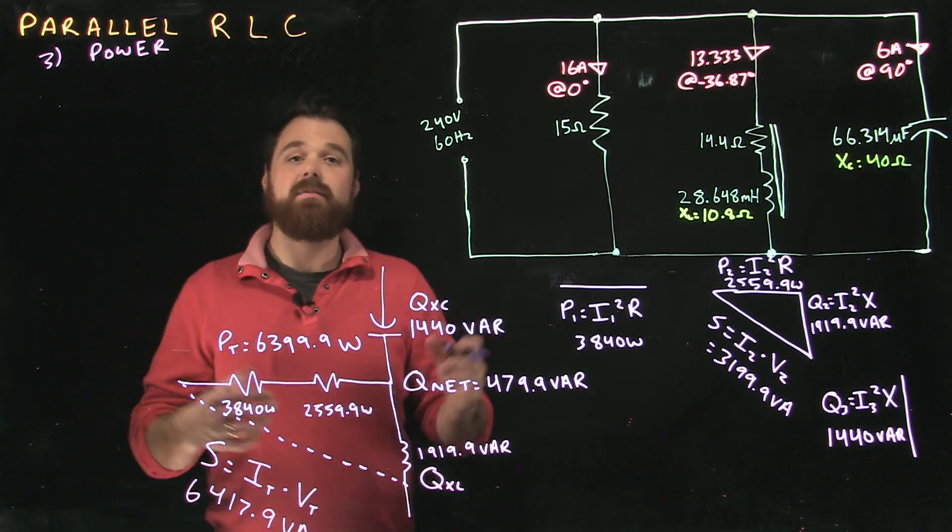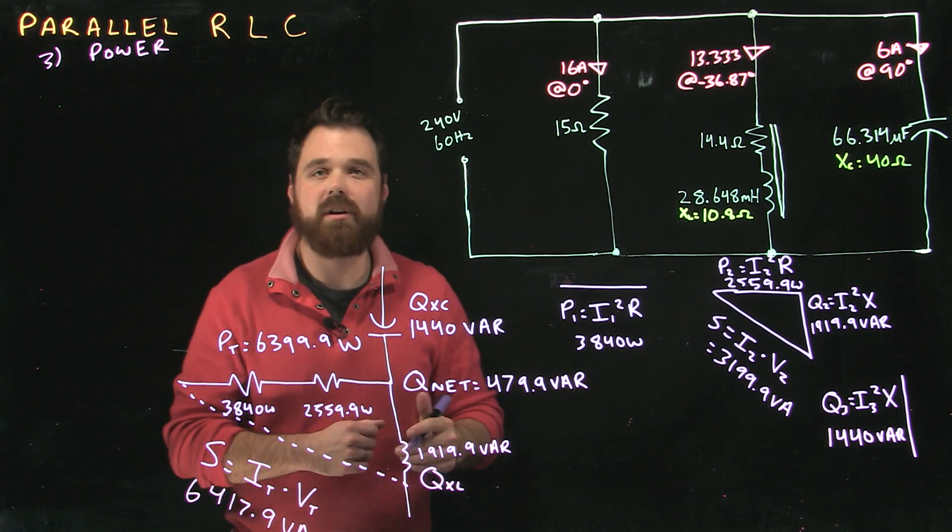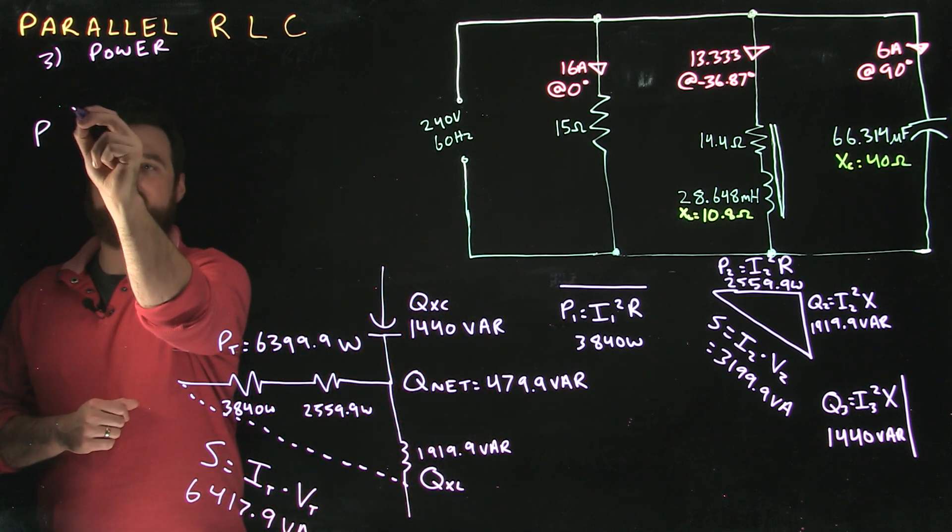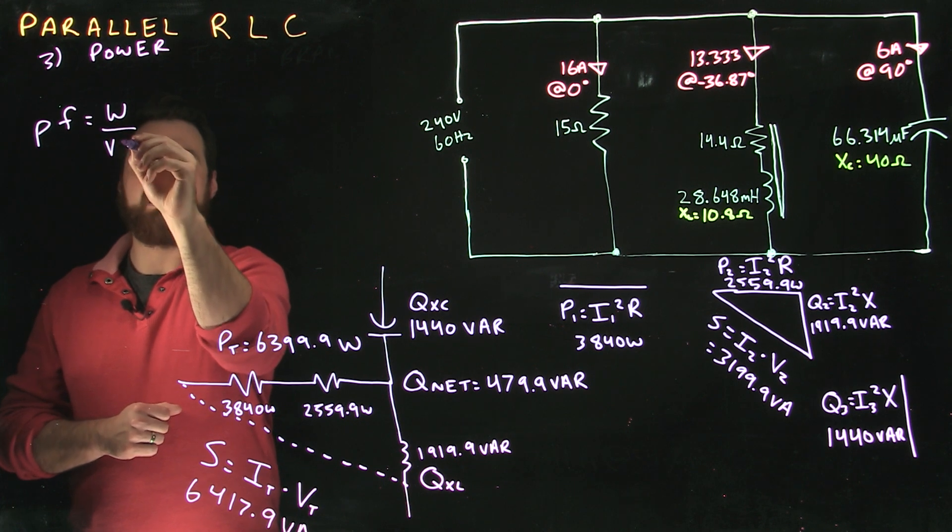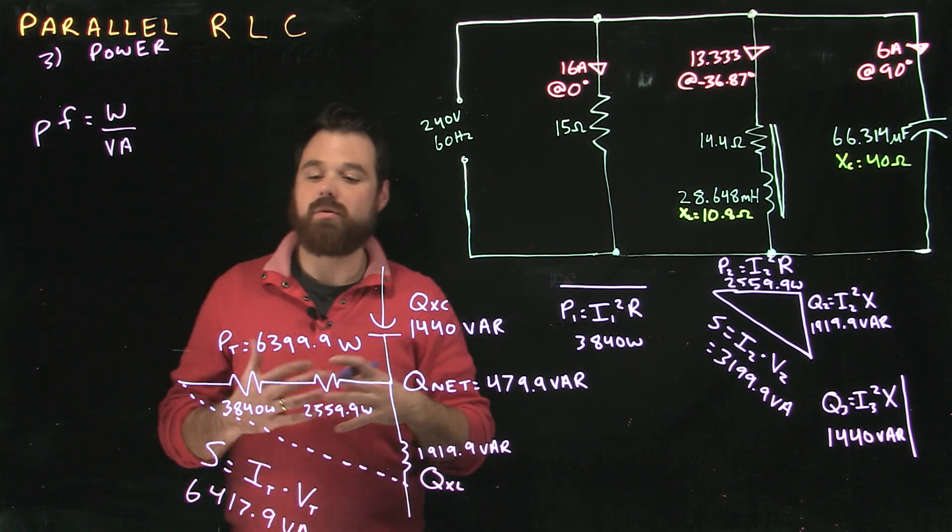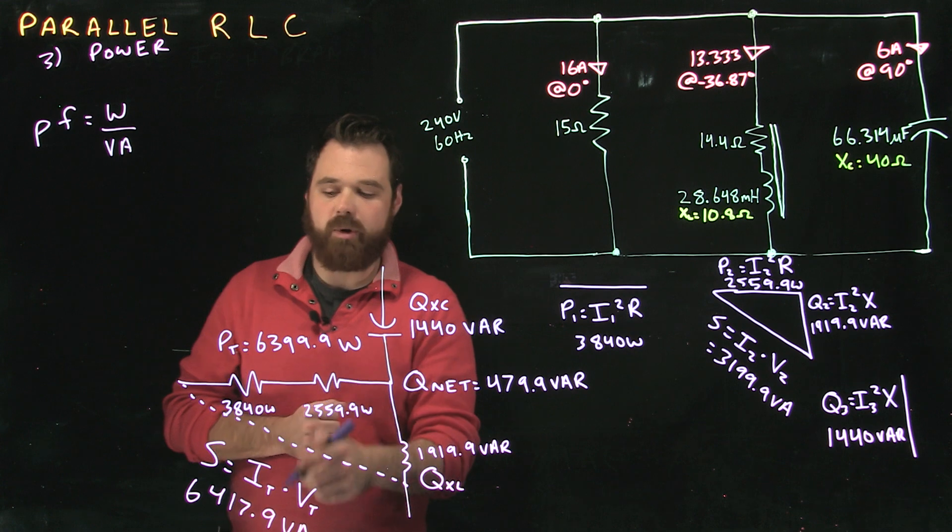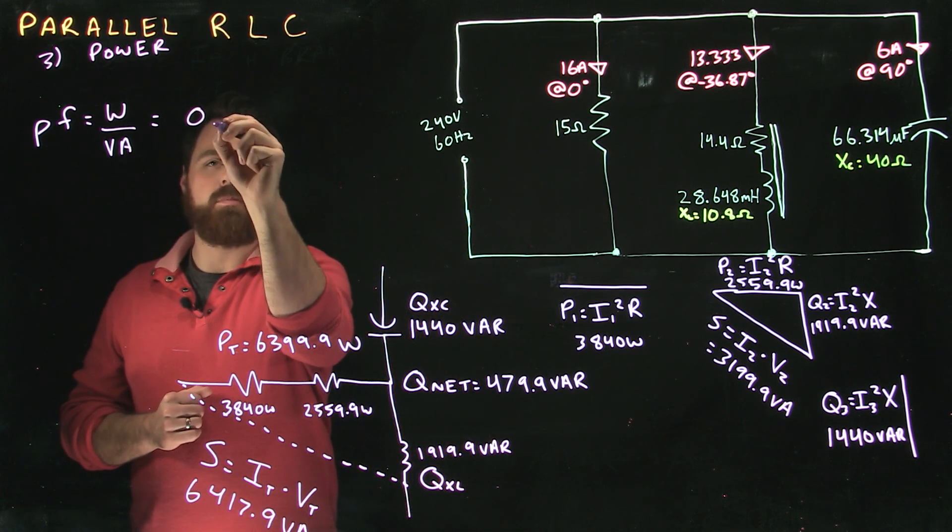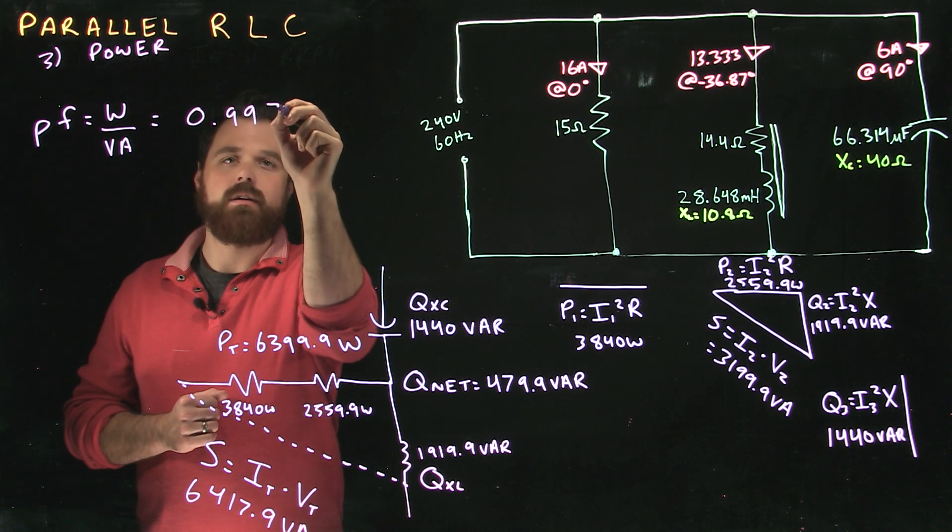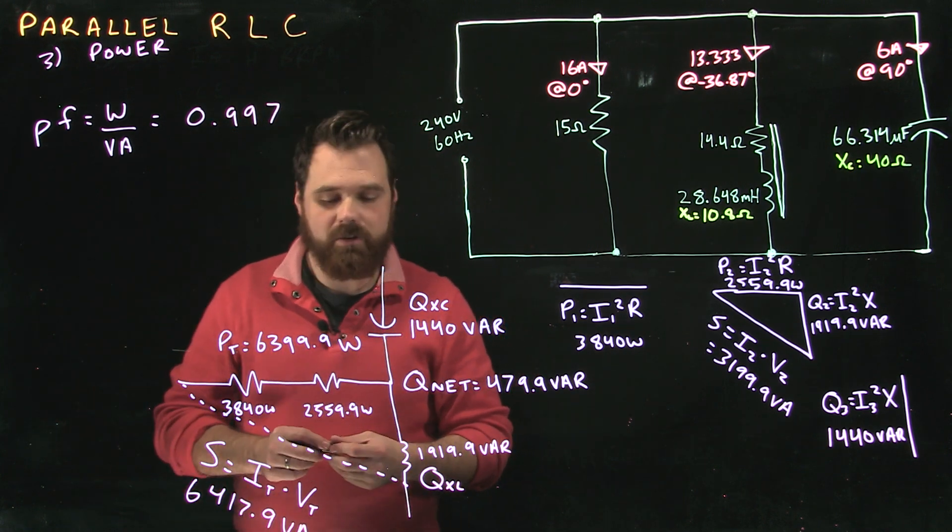Perfect. Now the very last step with all of these circuits is my power factor. It's going to be Watts divided by VA. So I go 6399.9 divided by my VA, and I get a power factor of 0.997, which is actually a very good power factor.